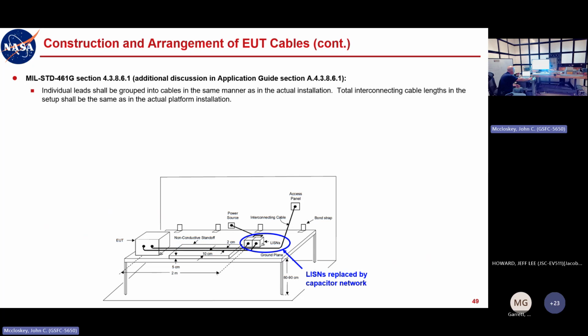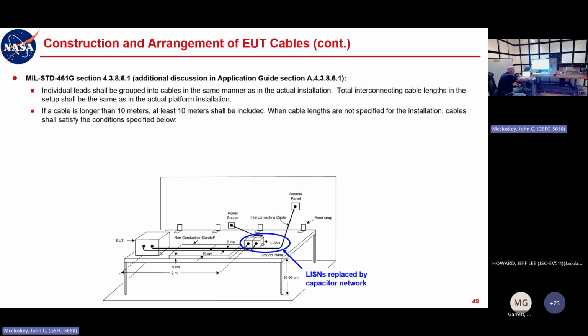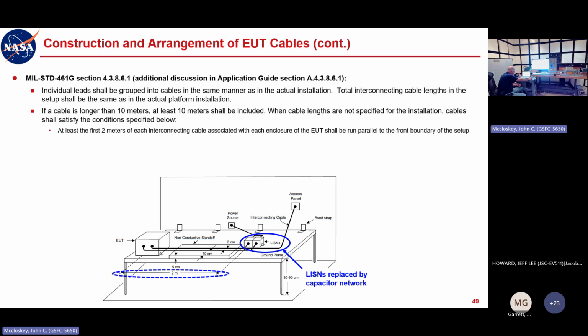Just some more about cables. This is the basic test setup diagram from the mil standard, directly from the mil standard. Where it says LISNs, we use the capacitor network for GEVS. Individual leads shall be grouped into cables the same way as in the actual installation. Total interconnecting cable lengths in the setup shall match the actual platform installation. That's the ideal, but sometimes you just have to take your best guess if you don't know those lengths when building your test cables. If it's longer than 10 meters, at least 10 meters shall be included, and so on.